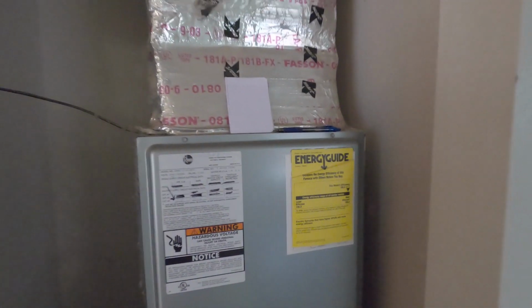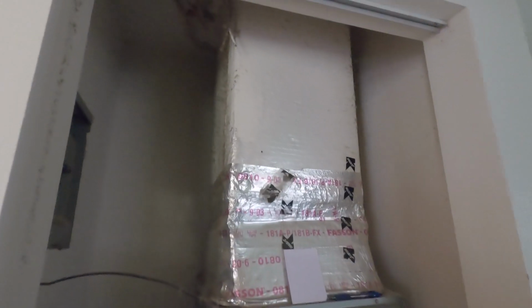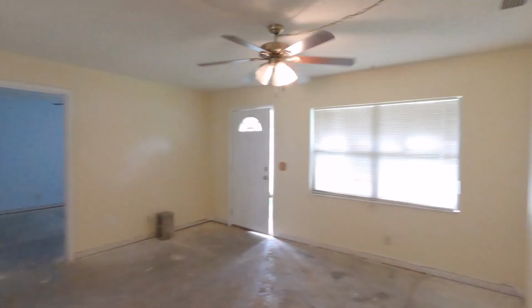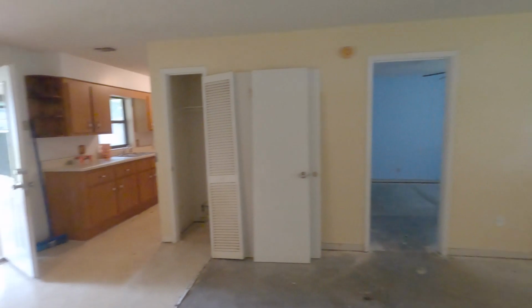I'm going to call the rental property people and let them know what I found, and see what they want to do. Hopefully they want to replace it, because ultimately they have multiple issues on the system. It's going to cost a lot of money just to repair it and get it back up and running, and we don't know if the other components are good - the fan motor, the compressor, if it's low on gas, stuff like that. So ultimately the best decision for them is to replace it and start fresh.